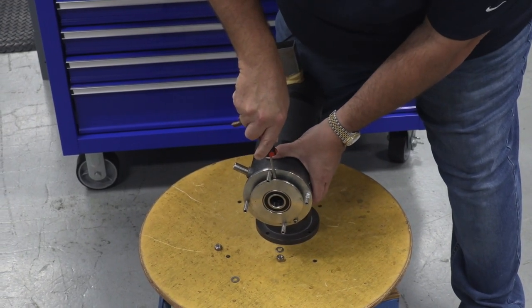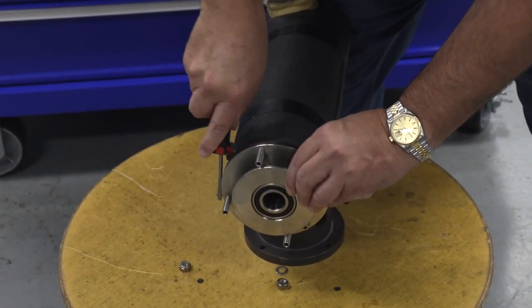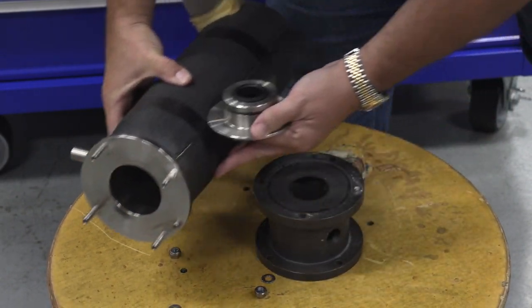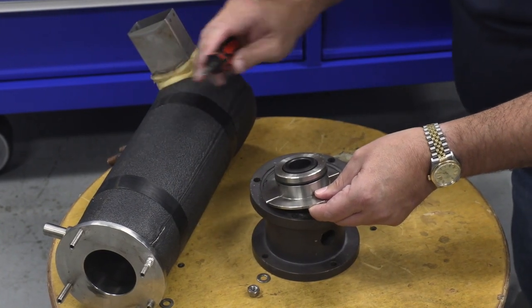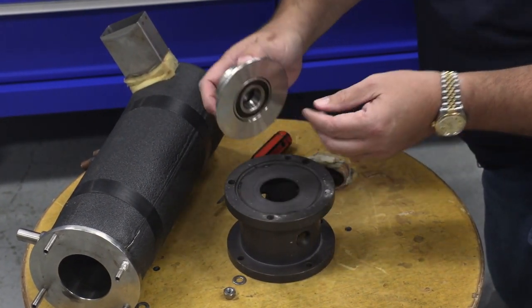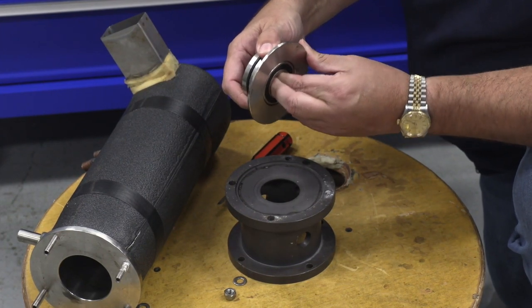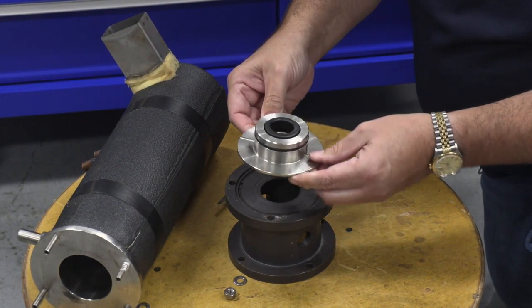I'm going to put a little flat-bladed screwdriver in there and take out the lower bearing assembly housing. The housing comes out — and focusing on this lower housing now — the bearing in the bottom normally will just slide right out, but as you can see this one's kind of seized in there. So I can just change this whole housing assembly.